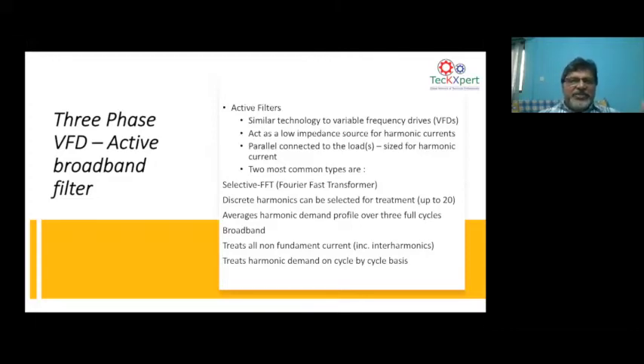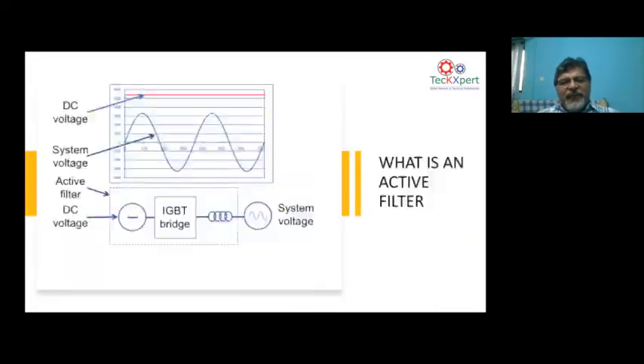Unlike the previous slide I was showing you for a VFD, where you put a filter at the terminal of the VFD, that's a series device. That means you have to break the cable. In a shunt device, you take an LV panel, take one of the outgoing breakers, and connect it to the active filter. That is how you connect a filter. Go to the slides.